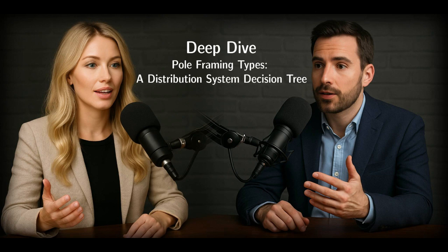In the field, you look for that visible sag of a suspended line, or, maybe more dramatically, the clear termination where the conductor's full tension is concentrated right at the insulator. Often you'll see the line visibly pulling against the pole or a crossarm. This instantly tells you, okay, we're dealing with high tension forces here.